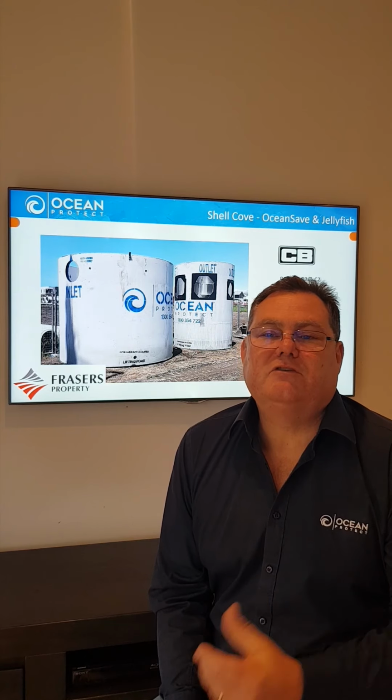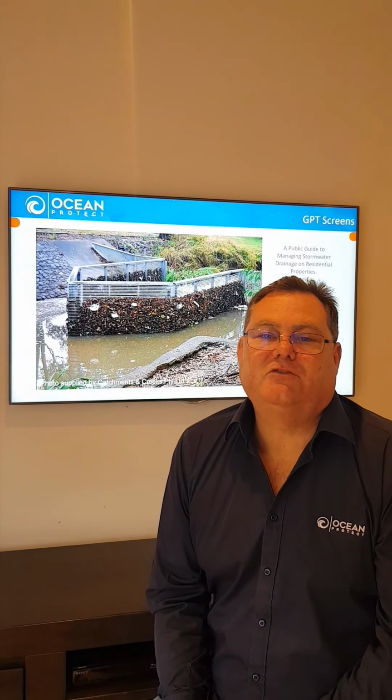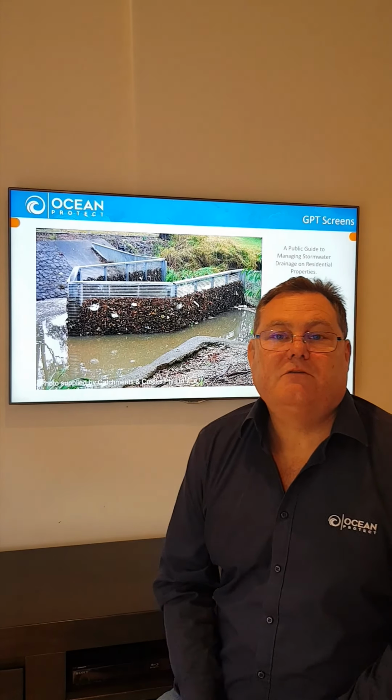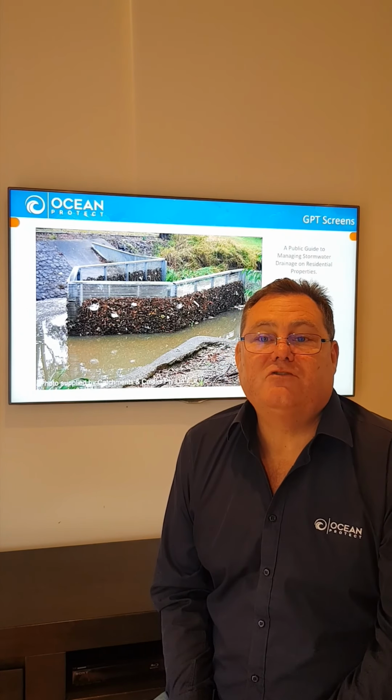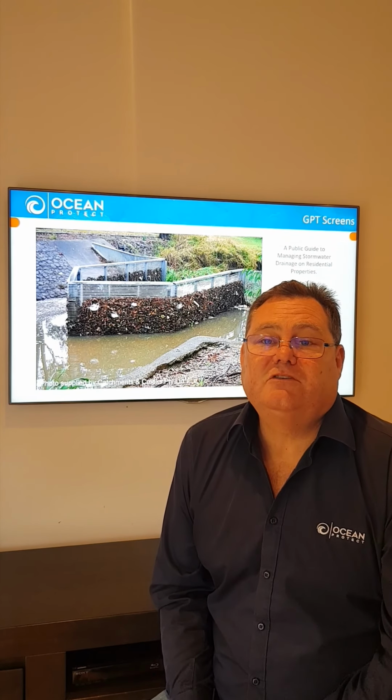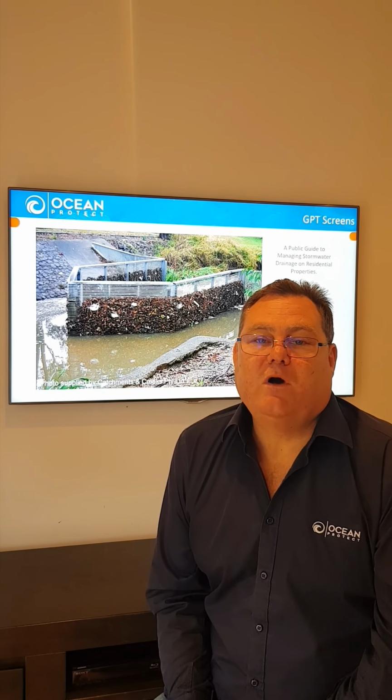Now, that covers some of the physical differences, but the biggest difference by far is that the OceanSave uses proven indirect screening technology rather than direct screening that is used by some other GPTs. So what is direct screening? Direct screening is when the water is forced to go directly through the screen. There are many GPTs that are used and still used today that are using direct screening in one way or another. Some are online using the horizontal or vertical bars that you saw there earlier, and others are in boxes or in manholes with screens that are installed above or below the water level.